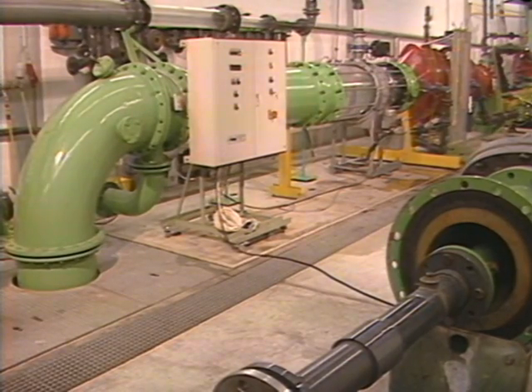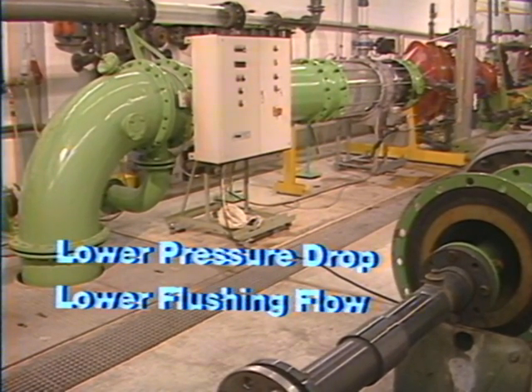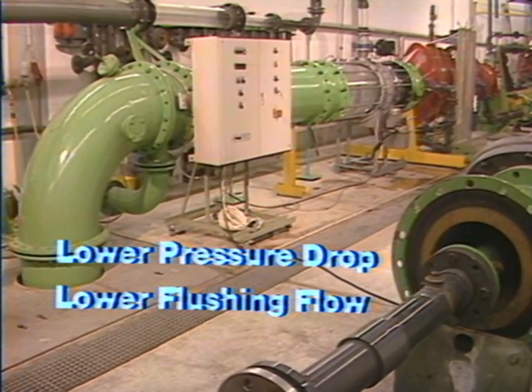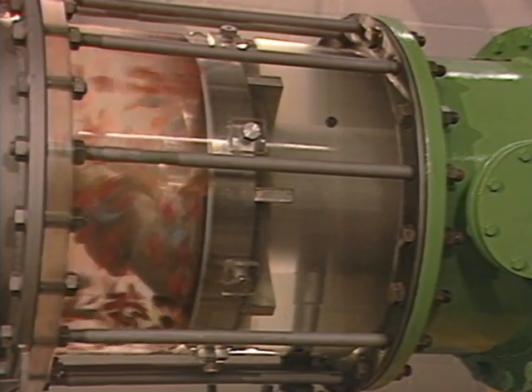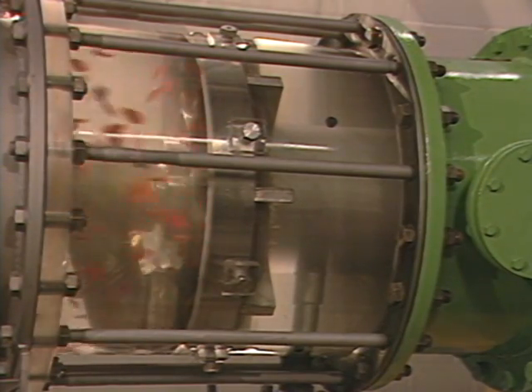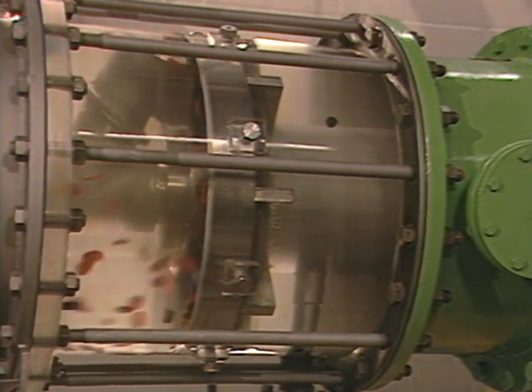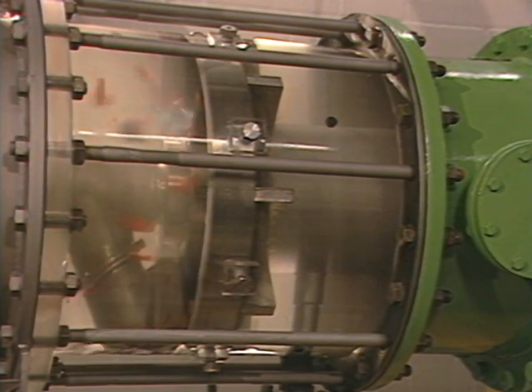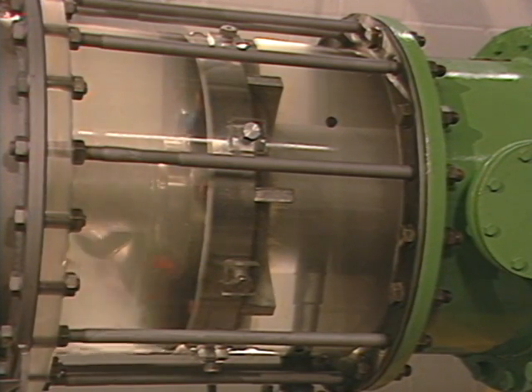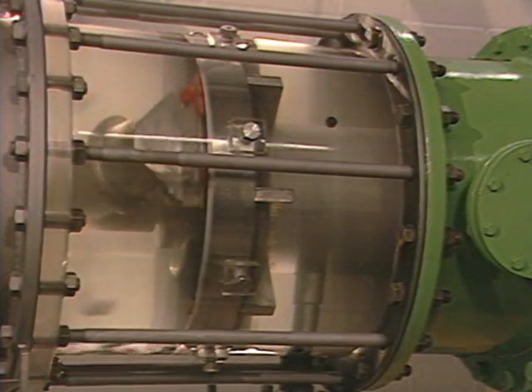The PR BW 800 offers other advantages like lower pressure drop and lower flushing water flow. In addition, its operating reliability and safety measure up to the toughest requirements — it copes easily with sudden in-rushes of large volumes of debris, one of the biggest hazards in power plant operation. The performance rate is the most meaningful criterion for the filter's inherent reliability.